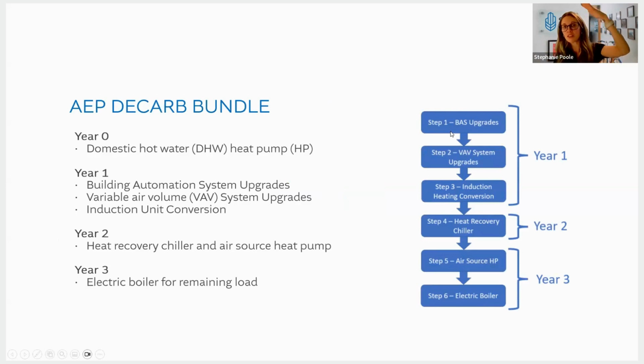The zero carbon plan starts with the building automation system - we're switching from constant volume to variable air volume. We're converting the induction units so instead of just cooling, they do heating and cooling, with more surface area so we can have lower temperatures. We're looking at a heat recovery chiller and an air source heat pump, and using an electric boiler for the remaining load - but it's very small, since it only covers the tiny bit of remaining load the other systems can't handle.